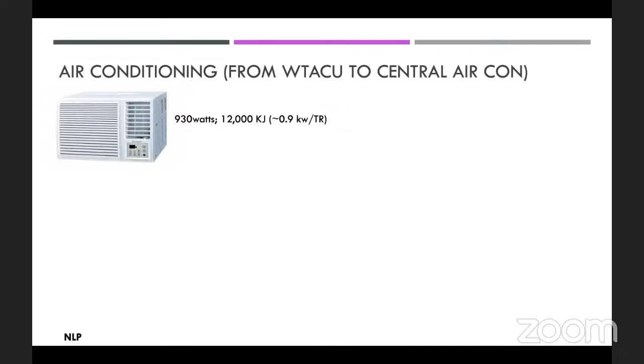One of the biggest projects undertaken was converting the window type air conditioning units. The hospital was built around the 1950s-60s, so typically the air conditioning was not centralized, working on window type units, which we know are typically not efficient. Its kilowatt per ton was about 0.9, that was the typical measurement.